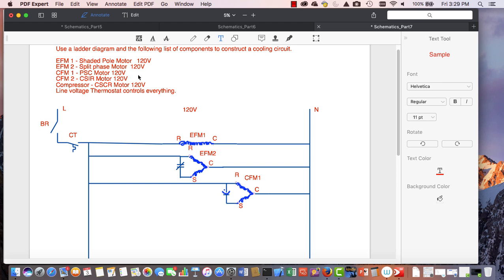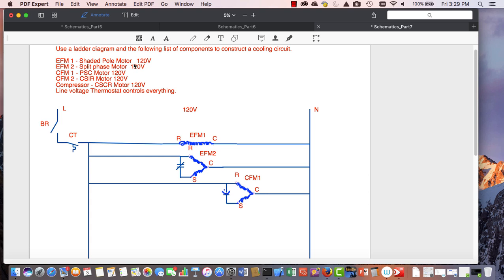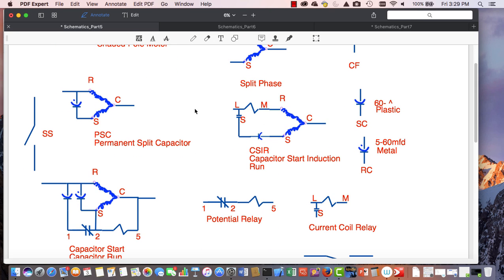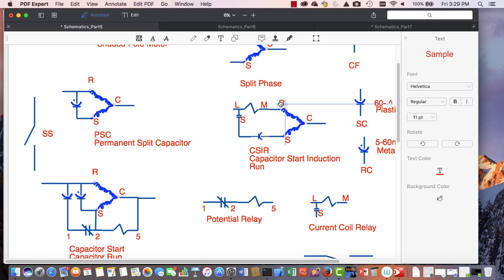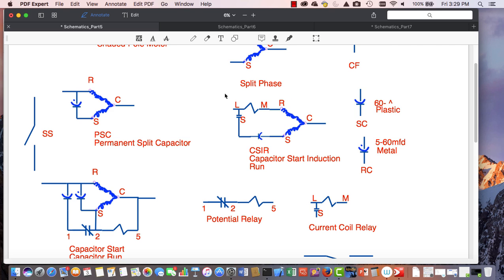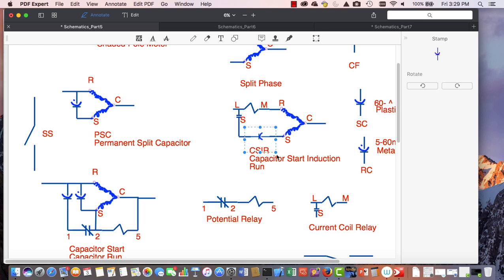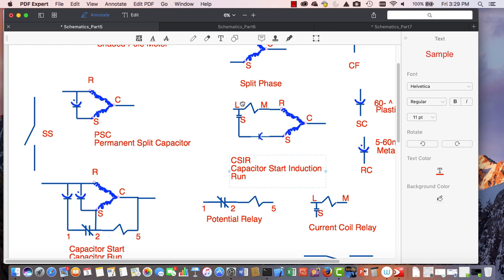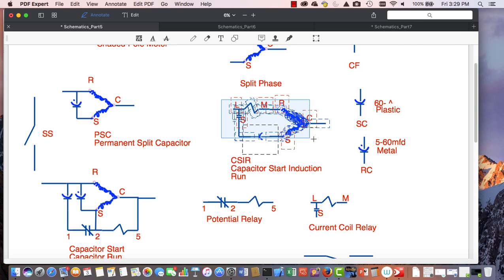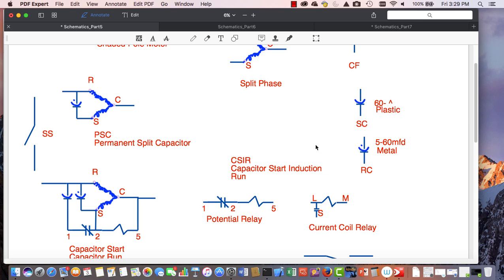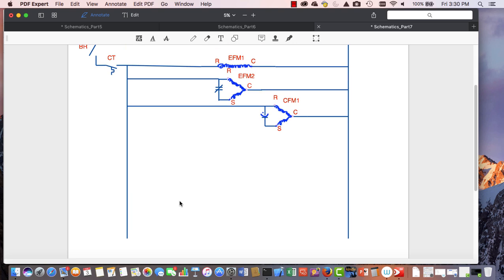Okay, now CFM2 is a CSIR. Remember, capacitor start, induction run. So this will have a start capacitor and some sort of starting component. So coming back over here, we see my motor that has my current coil relay in it. Okay, and a start capacitor. So again, I'm going to come in here. I'm going to just move that a little bit. I'm going to copy that, come back over to my current diagram.